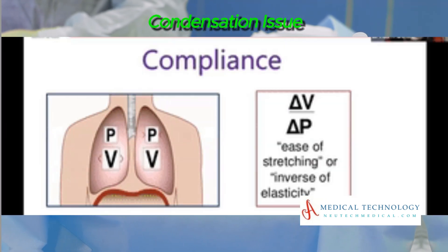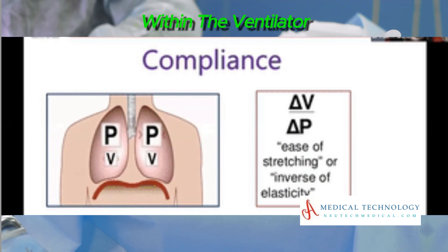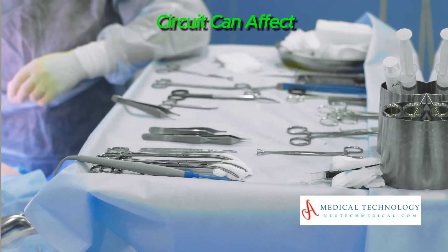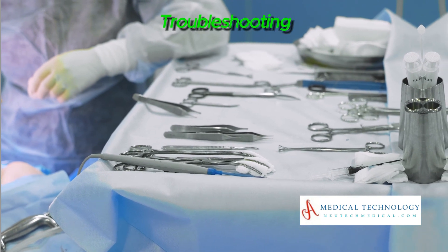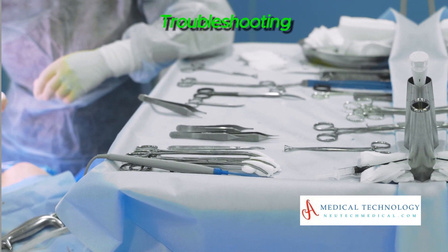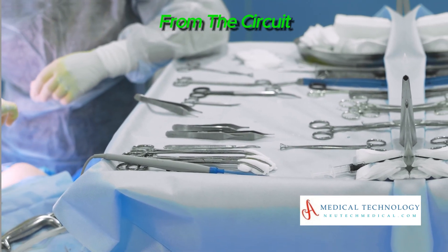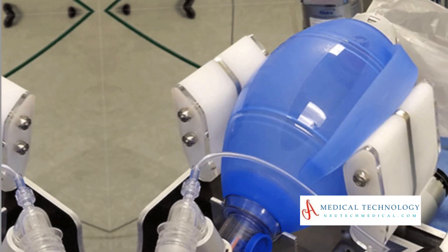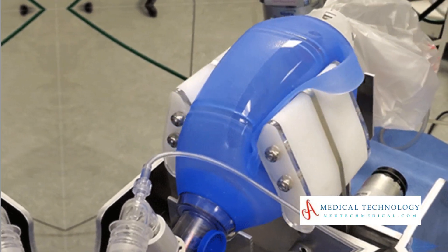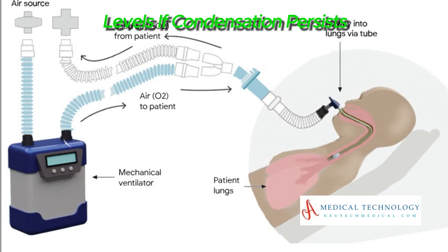Circuit Condensation — Issue: Condensation within the ventilator circuit can affect gas delivery. Troubleshooting: Drain condensation from the circuit, especially in humidified systems. Consider adjusting humidification levels if condensation persists.